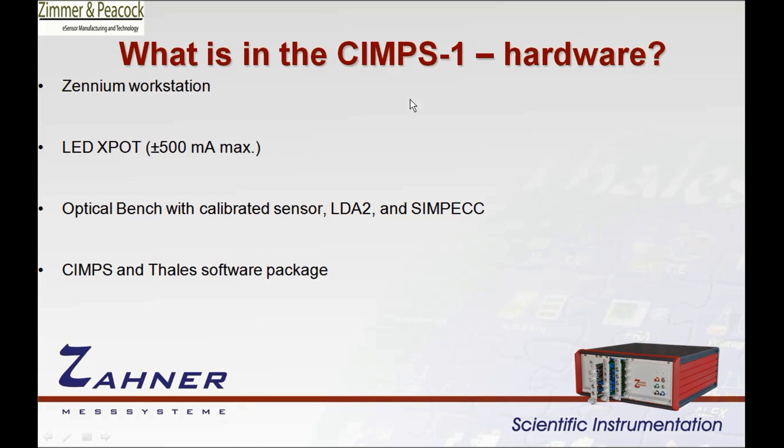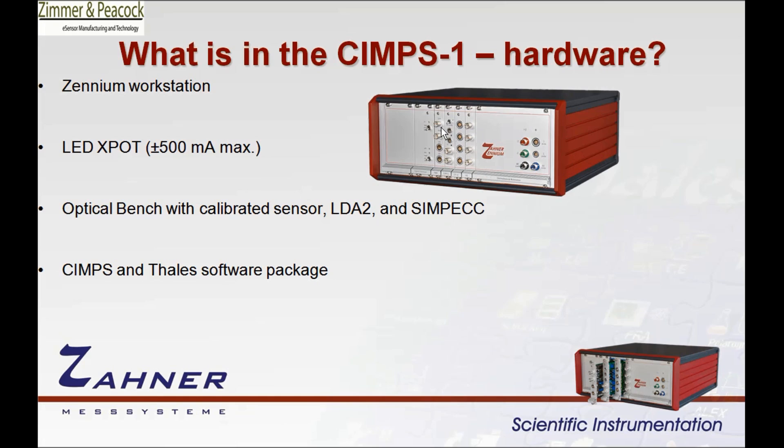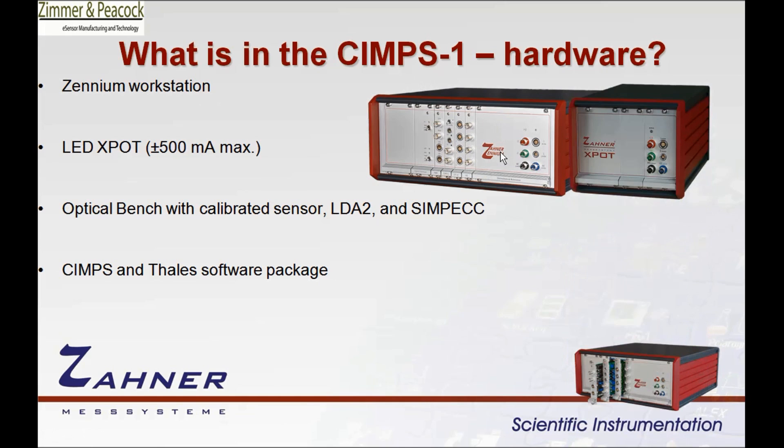This video is specifically about what's in the CIMPS-1 hardware. There's a Zennium workstation, which is an impedance spectrometer and a potentiostat/galvanostat combined. Some other systems, specifically the CIMPS-3 and CIMPS-4, have the IM-6 potentiostat, which is a slightly higher-grade potentiostat, but in the CIMPS-1 system you get the Zennium workstation. The next thing you get is the XPOT potentiostat, which is a slave to the Zennium system but also a standalone potentiostat. We use it as the power supply to the LDA-2.